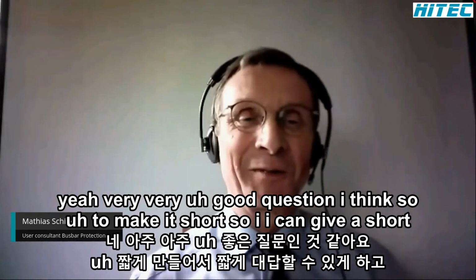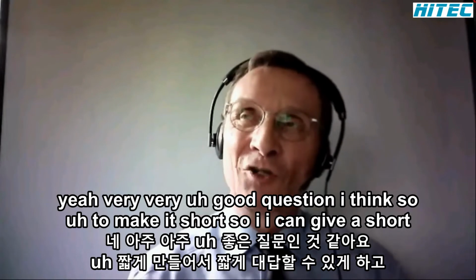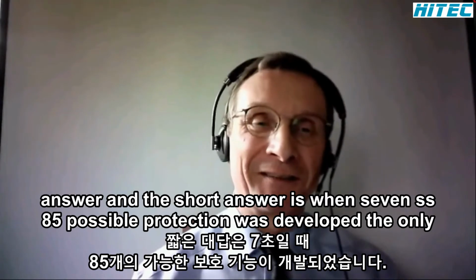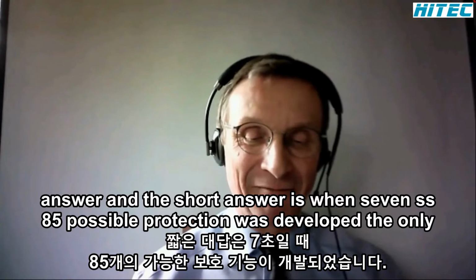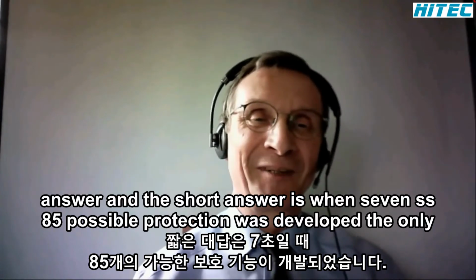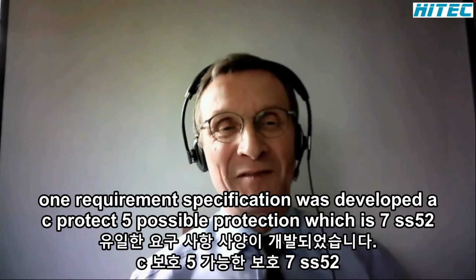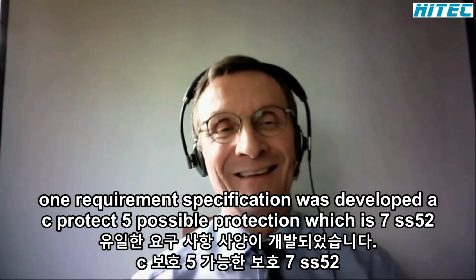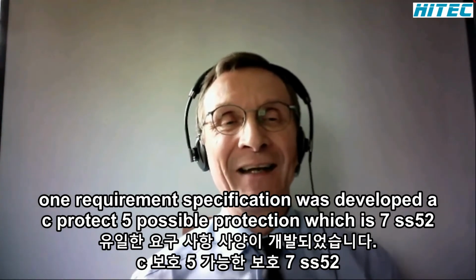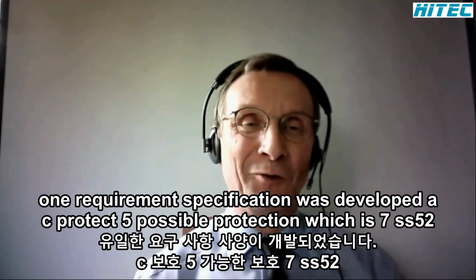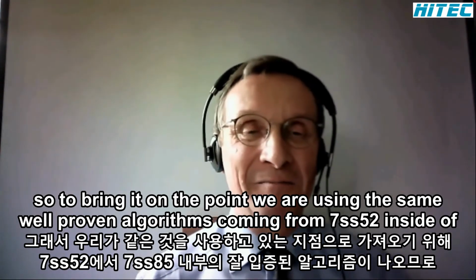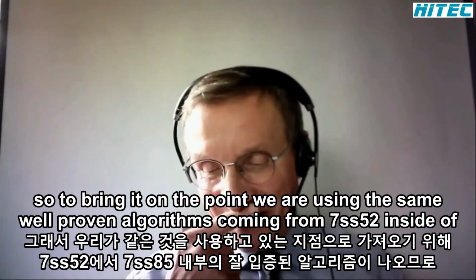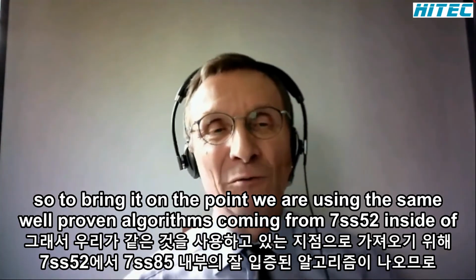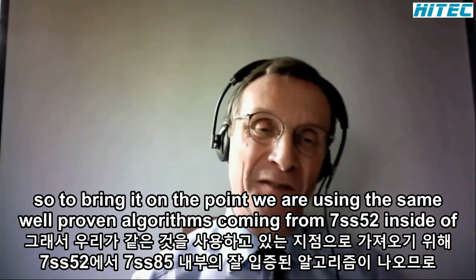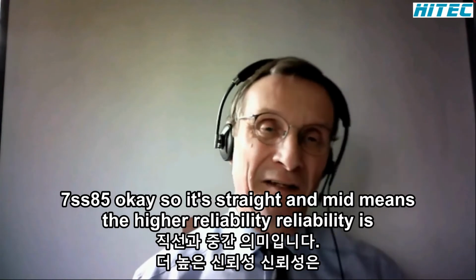Yeah, very, very good question. I think so. To make it short, so I can give a short answer, and the short answer is, when the 7SS85 busbar protection was developed, the only requirement specification was the SIPROTEC 5 busbar protection, which is 7SS52. So to bring it to the point, we are using the same well-proven algorithms coming from 7SS52 inside of 7SS85.